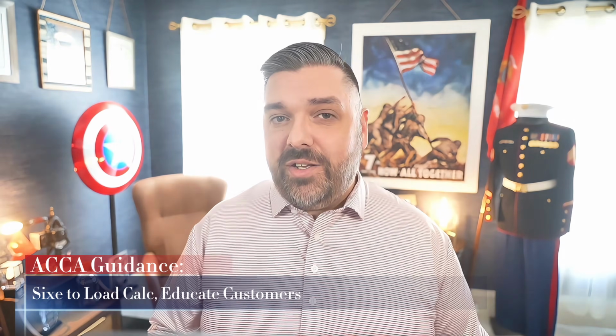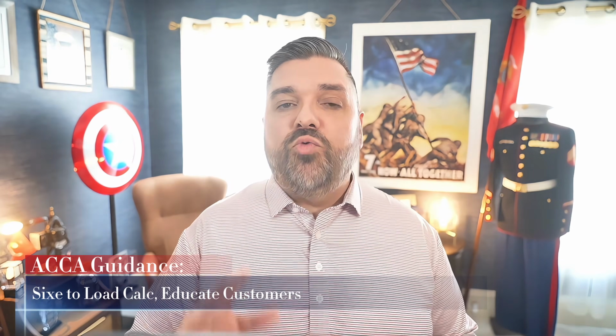Now, ACCA doesn't want you adding capacity for recovery load. The official guidance is to size to the calculation and educate customers about realistic recovery times. That's the right answer from an engineering standpoint. But from a customer satisfaction standpoint, you need to have a conversation about how they use their thermostat. If they tell you they regularly set it back 8 to 10 degrees, then you need to explain that the recovery is going to take longer with a properly sized variable speed system, compared to the oversized single-stage dinosaur they're replacing. Set that expectation up front, or you're going to deal with complaints later on.